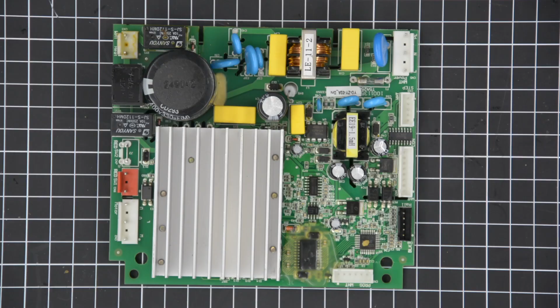Okay, let's break down what's going on with the printed circuit board. Starting with the power section, we can see massive filtering consisting of capacitors, coils and varistors. Those are for suppressing high inrush current, which is generated when the cold device is connected to the power line, and also for suppressing the electromagnetic interference generated by the machine.